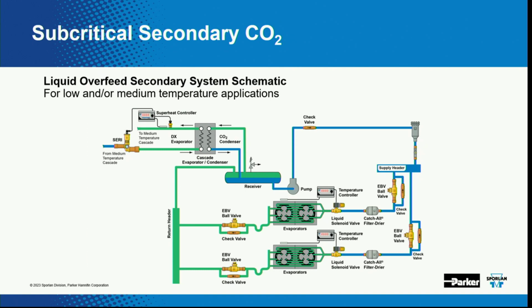Okay, so we talked about glycol. Now, this is secondary CO2, otherwise known as a liquid overfeed secondary system. And it looks kind of similar to the glycol loop. They put an extra case in here for good measure. But here again, we have basically a chiller up here on the top left, and that's what's going to do the primary cooling. And then the CO2 is being circulated in the system to take that cooling to the cases out on the floor. So this is using a pump. It's basically pumping liquid CO2 around the system.